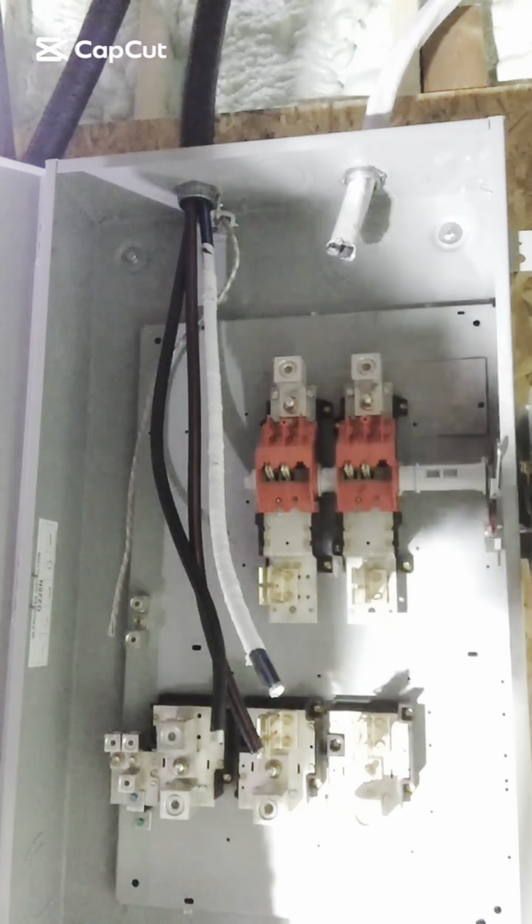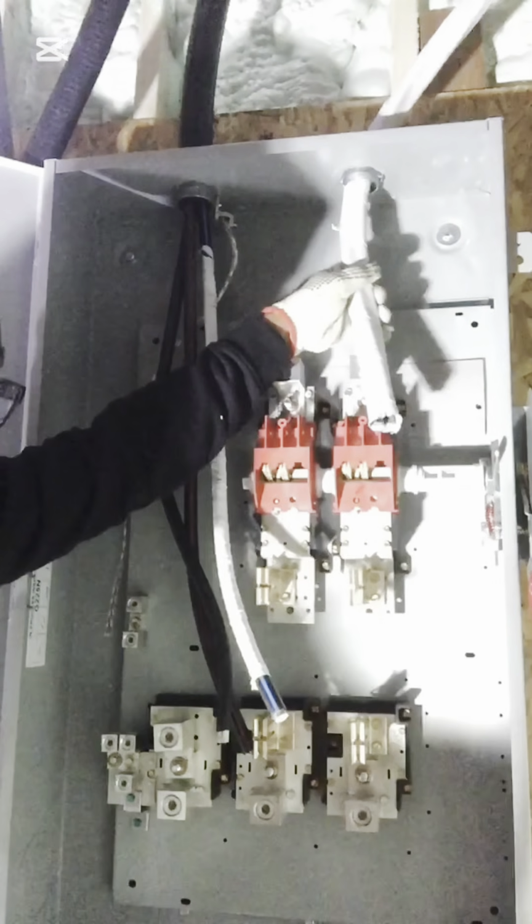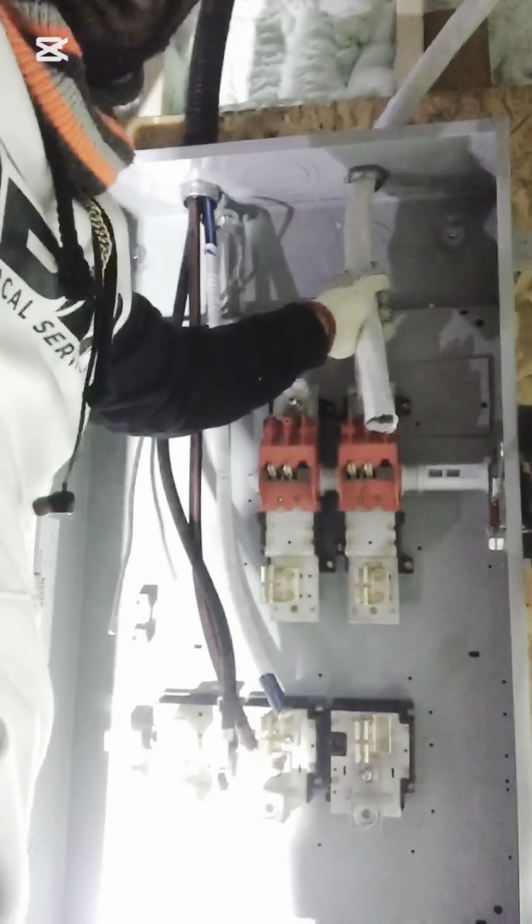So when it comes to parallel path, cables, 400 amp service installation, you always want to make sure that your cables are the same length. You also want to make sure that when you're running your parallel runs, if you do use certain cables like I am here, to identify your neutral conductors. Very important. First things first is to identify your neutral conductors.